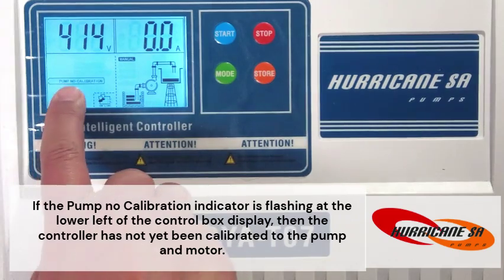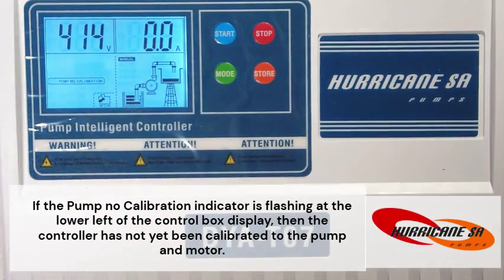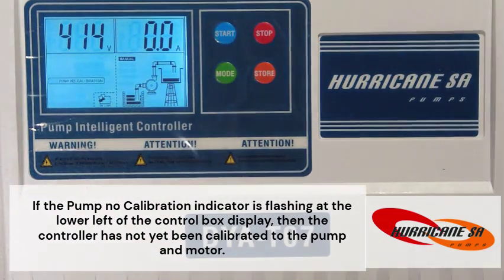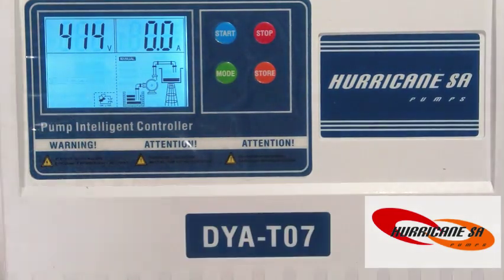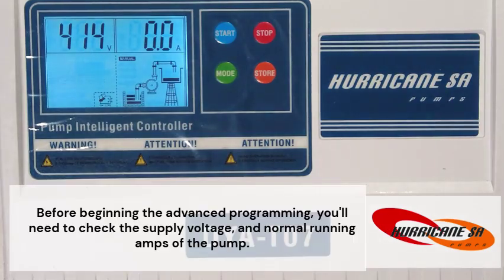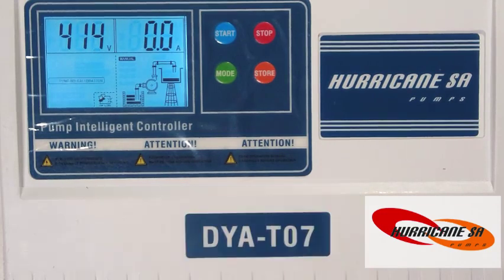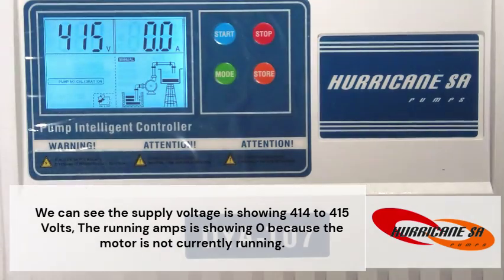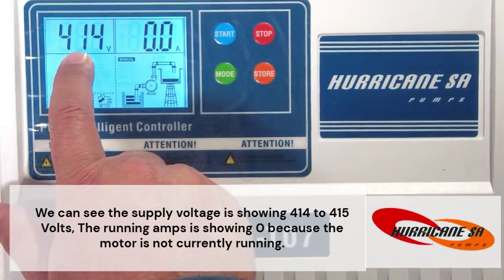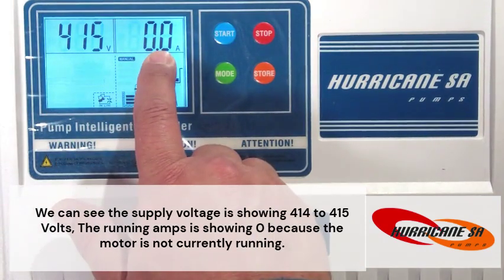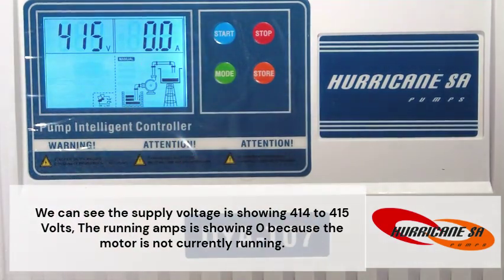If the pump no calibration indicator is flashing at the lower left of the control box display, then the controller has not yet been calibrated to the pump and motor. Before beginning the advanced programming, you'll need to check the supply voltage and normal running amps of the pump. We can see the supply voltage is showing 414 to 415 volts. The running amps is showing 0 because the motor is not currently running.